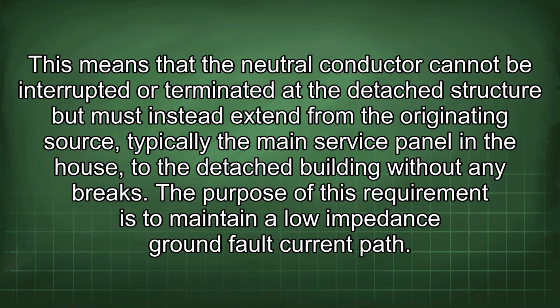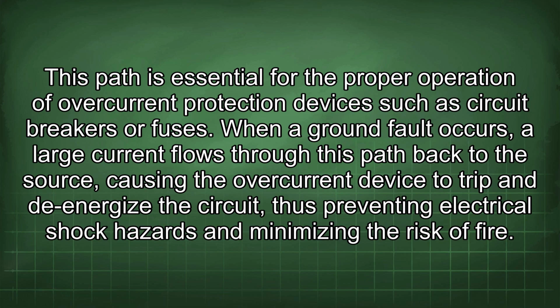The purpose of this requirement is to maintain a low impedance ground fault current path. This path is essential for the proper operation of overcurrent protection devices such as circuit breakers or fuses. When a ground fault occurs, a large current flows through this path back to the source, causing the overcurrent device to trip and de-energize the circuit, thus preventing electrical shock hazards and minimizing the risk of fire.